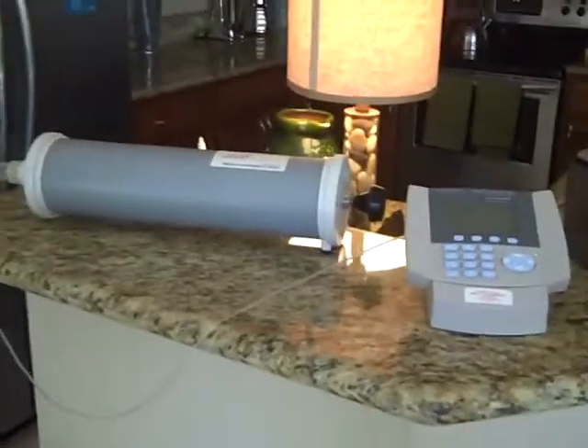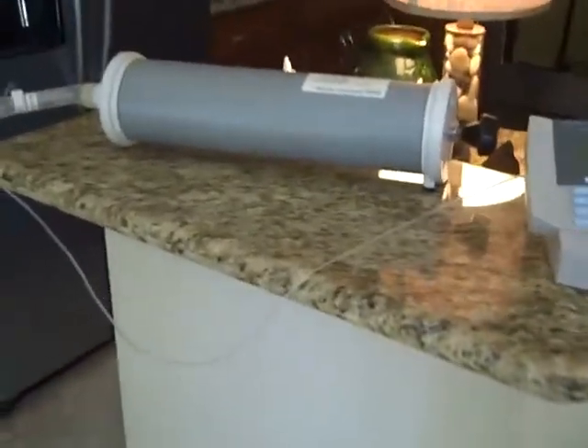At the top it'll have the date, the last cal check, and so just save this and again put a copy with every spirometer test you do that day. And then each new day, you have to do a calibration check at the beginning of each day. So you can see how I have this hooked up.